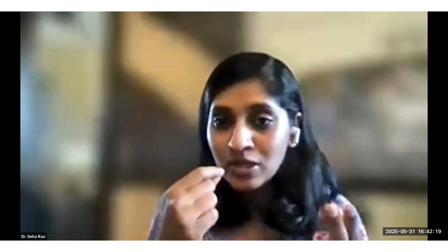The second thing we tell them: sometimes we increase the pressures that we're giving, because when you're sick, you generally tend to have a higher requirement. The third thing we commonly have problems with is connecting oxygen into the BiPAP machine, because every machine is different and most centers don't know where to connect the oxygen. Should we connect it to the mask? Should we connect it to the machine? That also we can help you with via a simple video consult.